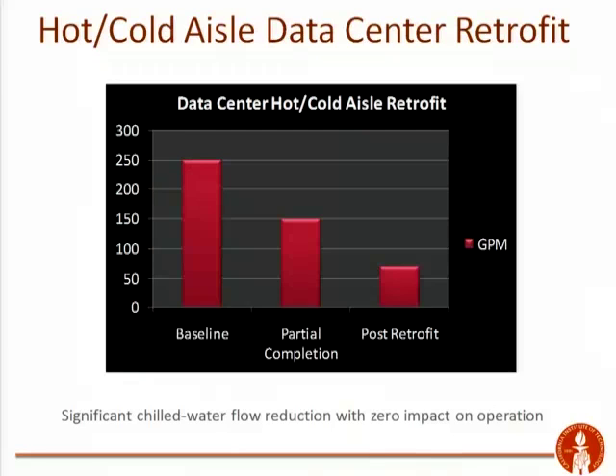Now, it's important to realize that because we studied that and said, well, something's wrong here. We're not getting the savings that we originally thought we would achieve. So we went back in and realized that the valves in that room were broken. The valves weren't opening and closing properly to supply that chilled water to the room. So we swapped out those valves, made that fix, and then boom, we were back at the post-retrofit, the predicted value that we wanted to get to.